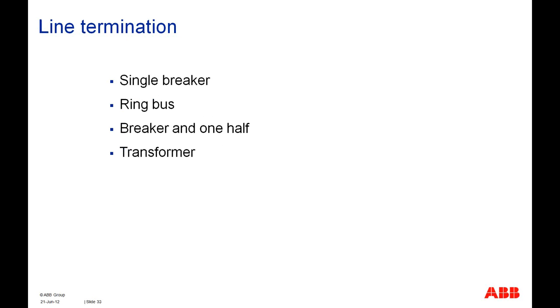Now let's talk about the line termination. So we can have a line differential protection scheme involving one breaker, for example, or we can have a ring bus or a breaker and a half scheme, or we can have a transformer also in the protection zone. And for each type of line termination, we have specifics which need to be taken care of.